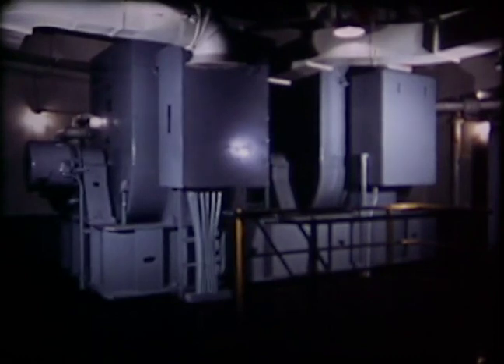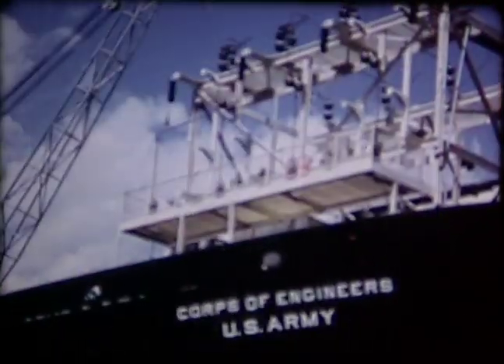Ship service electrical requirements are supplied by the turbine generator. When the plant is operated at 50 cycles, a frequency changer converts to 60 cycles the electrical requirement for powering the shipboard electrical demand. Power from the turbine generator passes through the switchgear to the transformers to the ship's transmission tower.